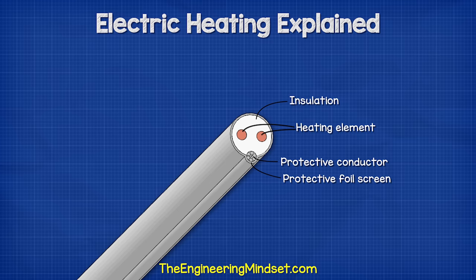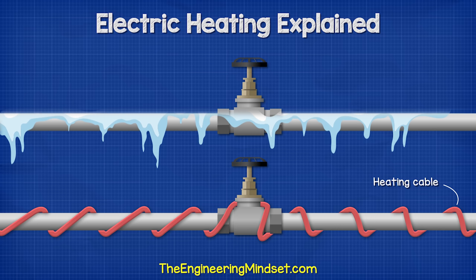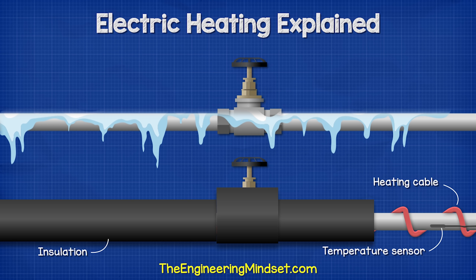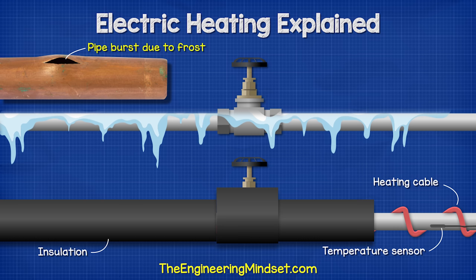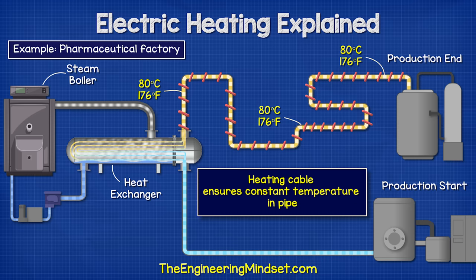We also find electric heating cables used for frost protection, typically along an external pipe which has the risk of freezing. The cable is installed along the pipe and fittings and is usually then insulated. Temperature sensors and thermostats will then monitor the pipes and ensure the fluid within the pipe stays above the freezing point, as this will otherwise damage the pipes. We can also use heating cables to ensure a fluid in a pipe remains at a certain temperature as it travels between various production points, for example food production or pharmaceuticals.